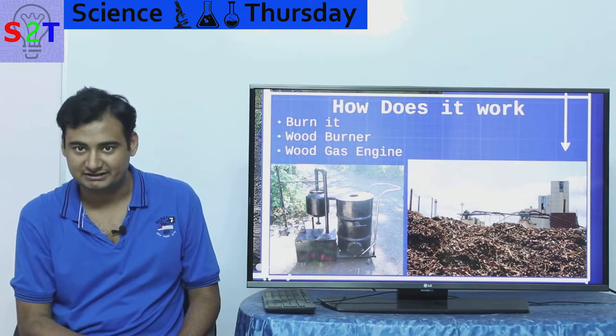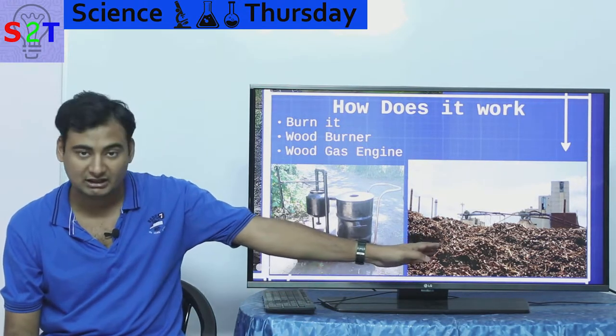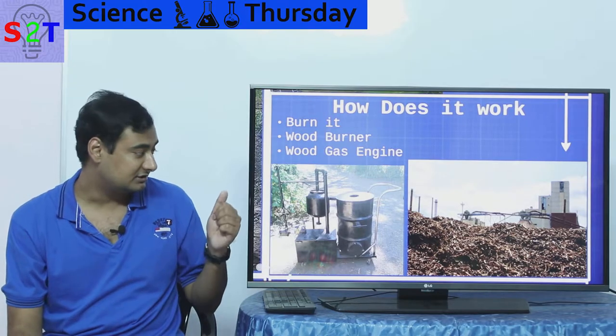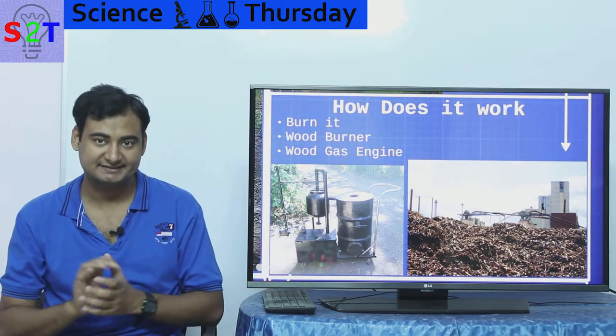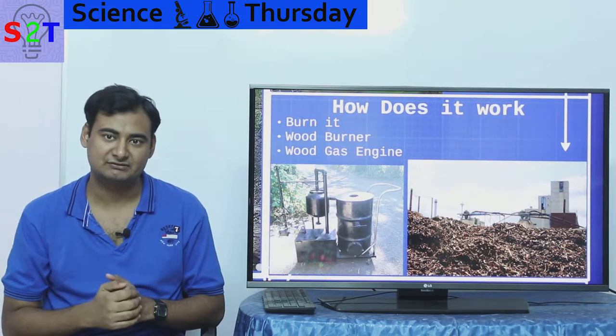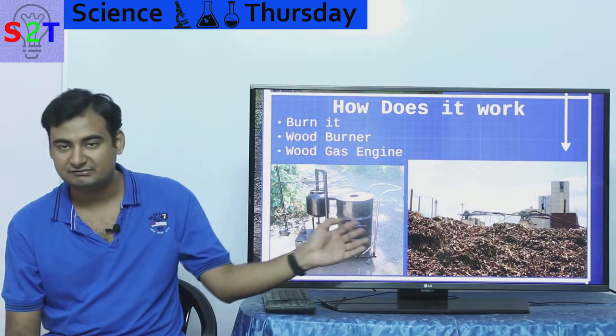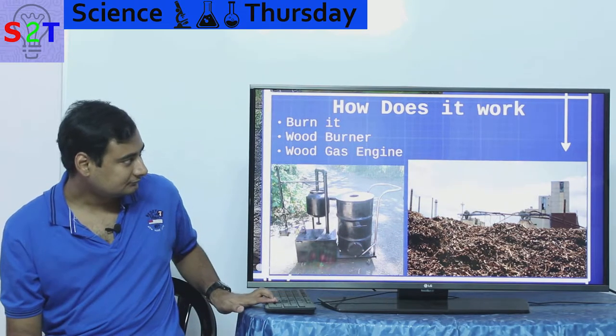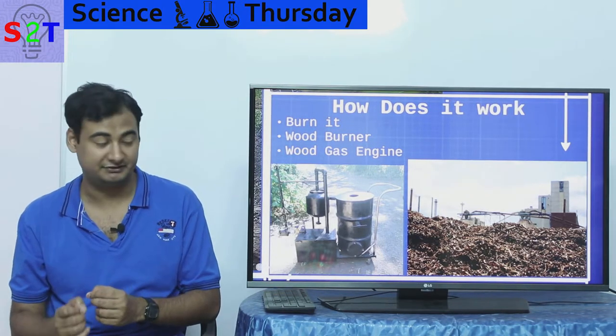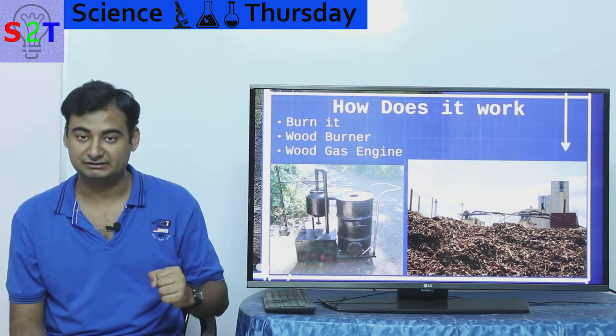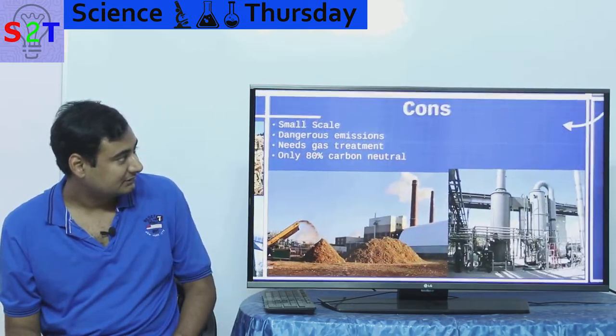So how does it work? It's very simple — we burn it. There are generally two structures: you can break wood down into chips and burn it directly, or you can convert it into wood gas, which contains some percentage of methane, some carbon monoxide, and some nitrogen. Burning them gives you power. Each approach has pros and cons — burning gas does not give you particulate emissions, while burning wood directly does not give as high nitrous oxide emissions as wood gas does.